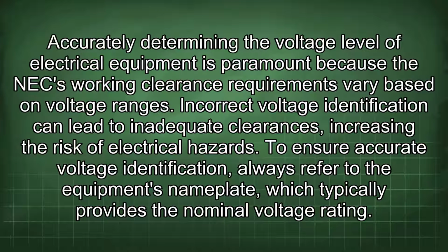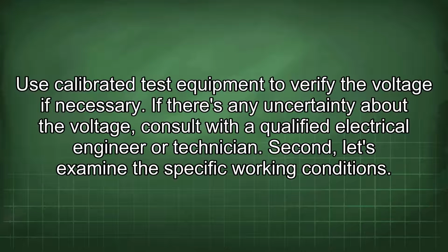Accurately determining the voltage level of electrical equipment is paramount because the NEC working clearance requirements vary based on voltage ranges. Incorrect voltage identification can lead to inadequate clearances, increasing the risk of electrical hazards. To ensure accurate voltage identification, always refer to the equipment's nameplate, which typically provides the nominal voltage rating. Use calibrated test equipment to verify the voltage if necessary. If there is any uncertainty about the voltage, consult with a qualified electrical engineer or technician.